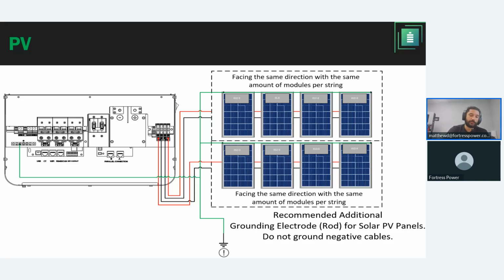But continuing, you would do that single string into MPPT1, assuming this string, it would be onto MPPT2, and then this string onto MPPT1. Remember, positive and negative, negative and positive, where the ground should land on a grounding electrode rod and not directly into the inverter. You want that if something were to happen, it goes into your grounding run first, right, per NEC code.